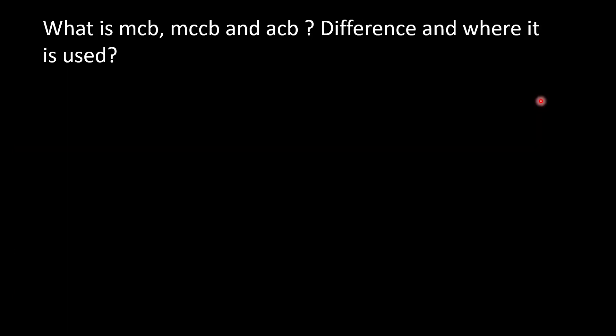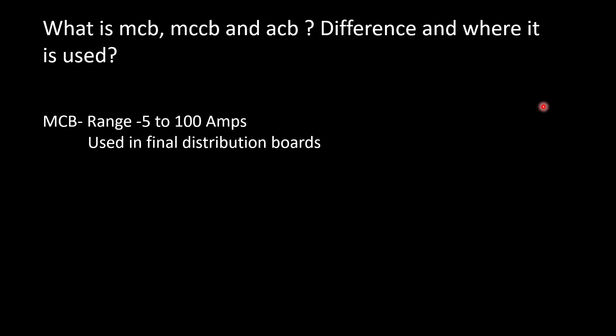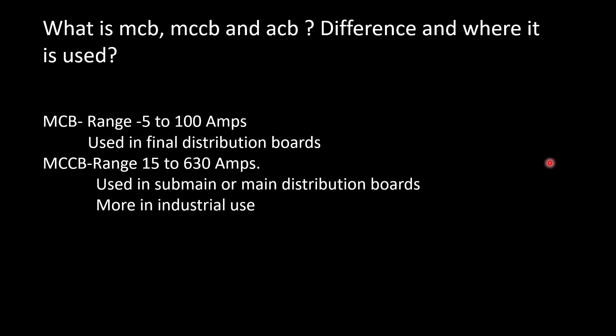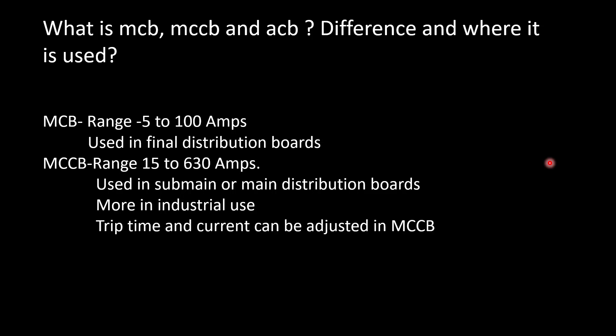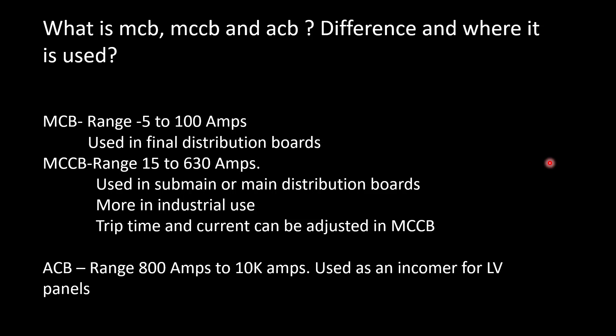What is MCB, MCCB, and ACB? What is the difference between them and where is each used? I have covered this subject in a detailed video — I will provide the link in the description box. MCB — full form is Miniature Circuit Breaker. It ranges between 5 to 100 amps and is used in the final distribution board or the distribution board inside villas and apartments. MCCB — Molded Case Circuit Breaker — ranges between 15 to 630 amps. It is used in sub-main distribution boards and is more common in industrial use. The key difference: in MCCB, the trip time and current can be adjusted; in MCB, it is not possible. ACB — Air Circuit Breaker — ranges between 800 amps to 10,000 amps and is used as an incomer for LV panels. Air is used to quench the arc produced due to ionization.